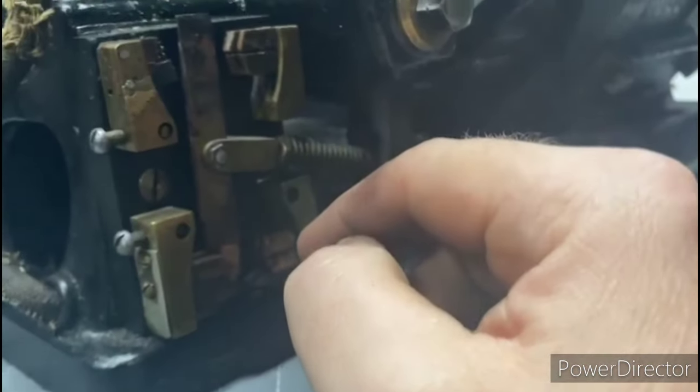Looking at the windings, we can see that insulation is missing in several areas, and that's going to have to be fixed for it to be running optimally. I haven't checked this with the Megger yet, but just on visual inspection for the age of it, it looks pretty good. I don't see any catastrophic flaws — nothing that looks fatal. It just needs some TLC, and it's going to be a delicate operation to bring it back to life. We're going to go ahead and take a bunch of pictures right now — I'm going to photograph every square inch of this thing, because once you have all these pieces taken apart and come back to it later, it can be really confusing. So we definitely want reference photos when we're putting it back together.